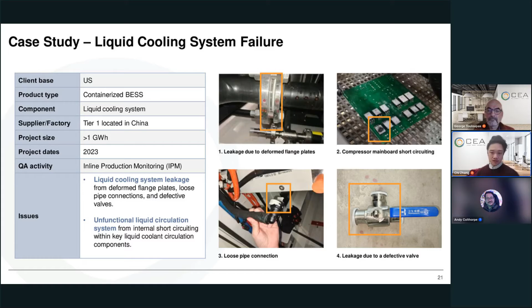equipment. So with liquid cooling system failure, any sort of leakage can develop into internal short circuiting on the DC bus within the container. And that, of course, can initiate an arcing event and eventually lead to a thermal runaway event. And component failure in the coolant circulation system usually can result in an extended period of system downtime. Usually, a properly working TMS, thermal management system, is a prerequisite for running the batteries to charge and discharge.